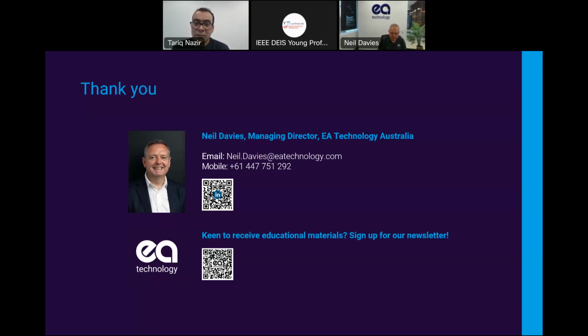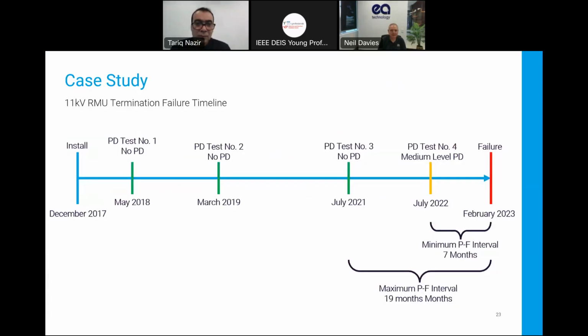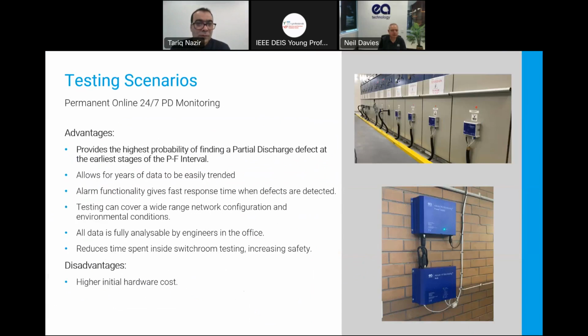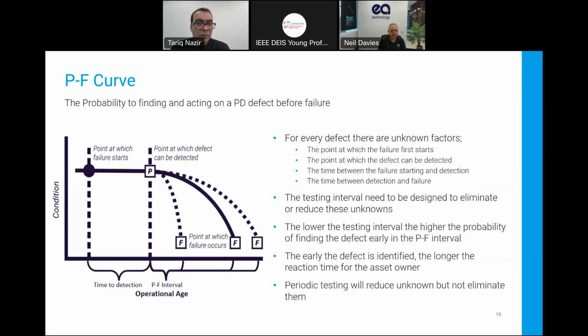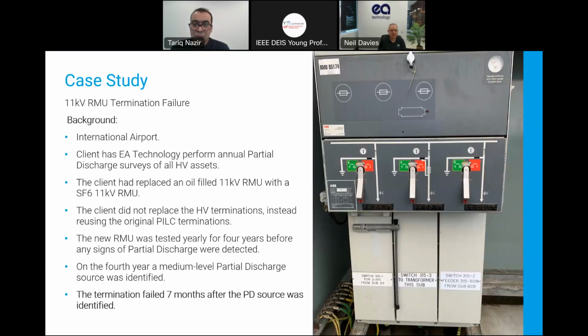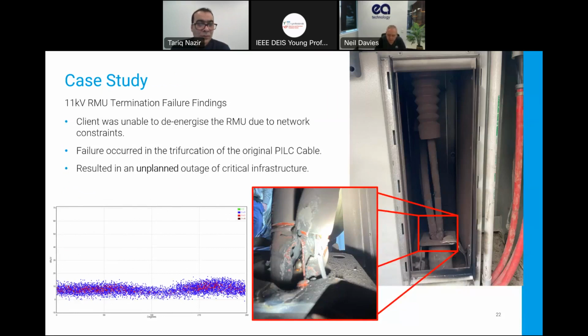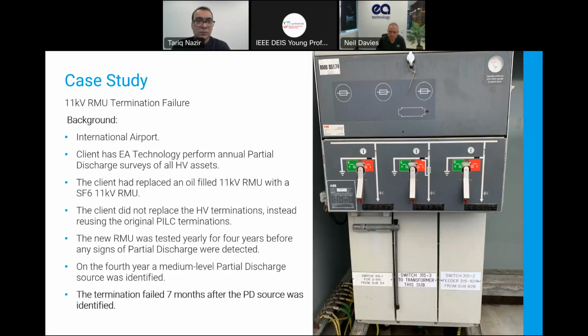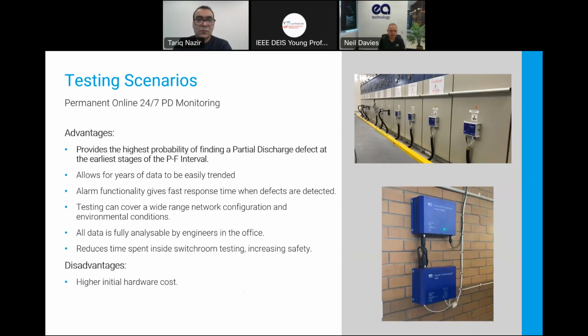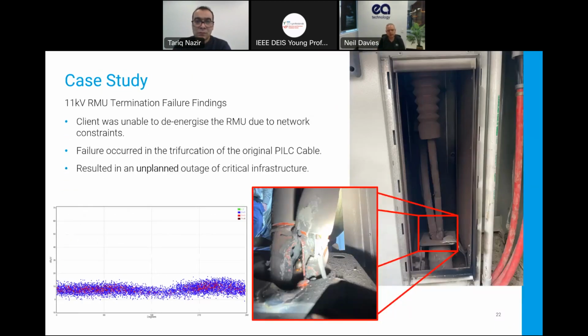The case study 1, I'm going to flip back to it because I think it was actually not a TEV, Greg. Sorry, I'm button happy. Right, so no, it's an ultrasonic one. Because it's surface to surface in that spacing on the cable, that's 20 or so decibel microvolts, so that's an ultrasonic measurement. If I remember rightly, we did find some TEV on there. The background reading on this network is usually about 5 dB, so very, very low, so it's easily identifiable. But this particular trace that we've got here is an ultrasonic trace.